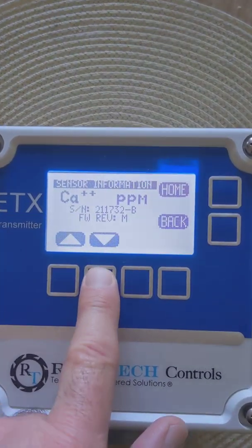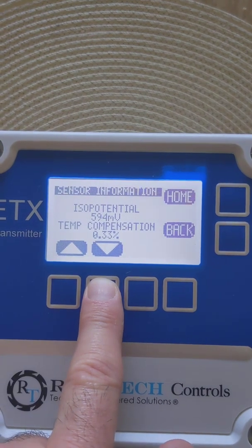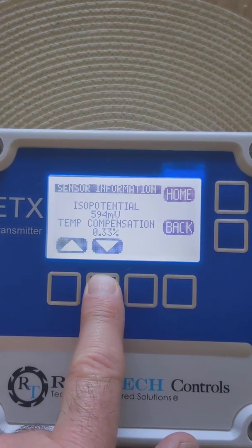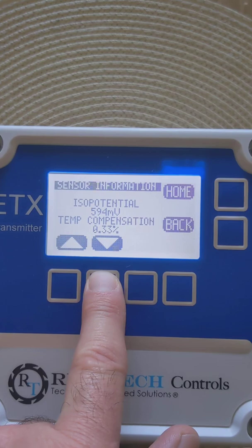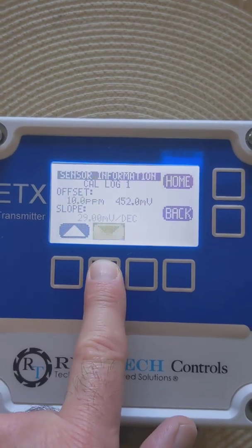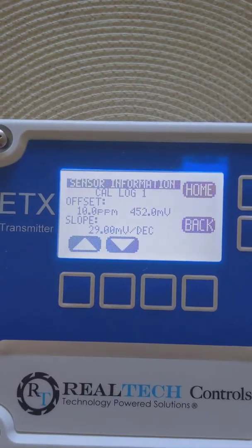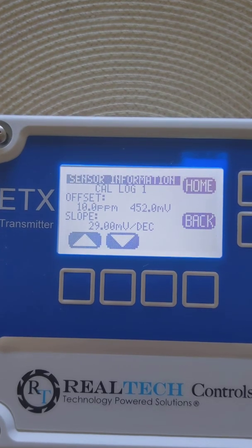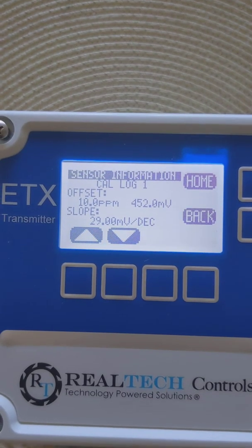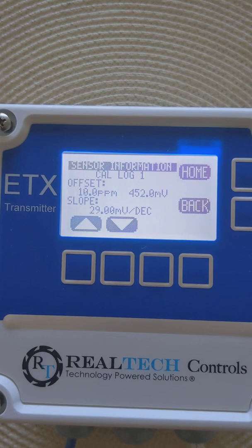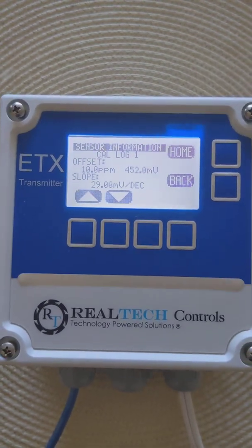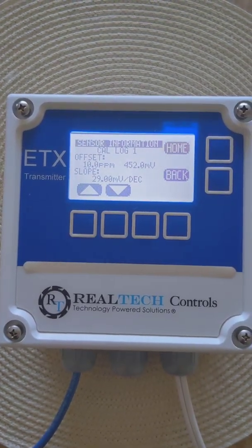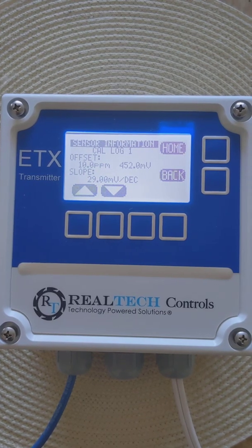and if you scroll down, that is the serial number, that is the ISO potential, the temperature compensation as per factory calibration, and you'll find log 1 where the offset is 10 ppm, 452 millivolts and 29 millivolts per decade. You want to record those values just in case you do a calibration and you want to reset the sensor to the factory default values.